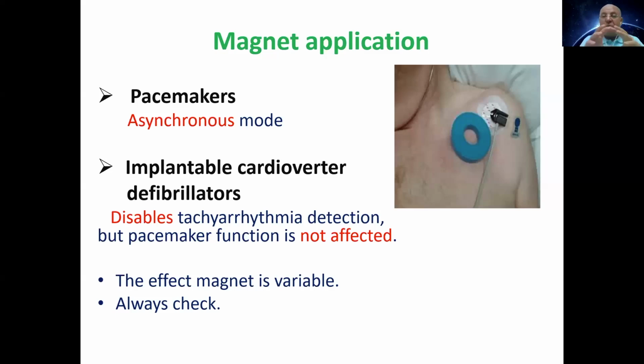Keep in mind, all the new generations of the ICD are ICD plus pacemaker. CRT is a CRT ICD plus pacemaker. Okay, pacemaker alone is something else. An ICD or CRT usually has a pacemaker. So for the ICD, the magnet disables the tachyarrhythmias, but it will not affect the pacemaker. So if you need to deactivate the pacemaker of a patient with an ICD, you have to put an external pacemaker. Okay, I hope this is okay.